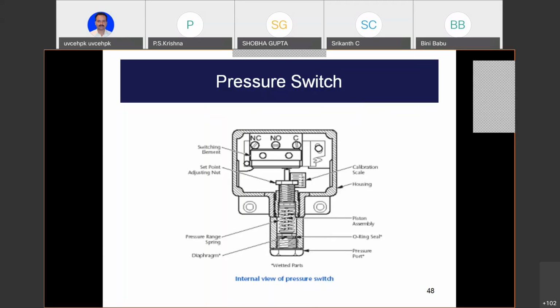That is, the pressure is healthy. If the contact is open, when the pressure drops, in our case, for this example only, it's unhealthy. For this example, compare it with that plant we designed. So it's like this: no pressure, dangerous; healthy pressure, so okay.